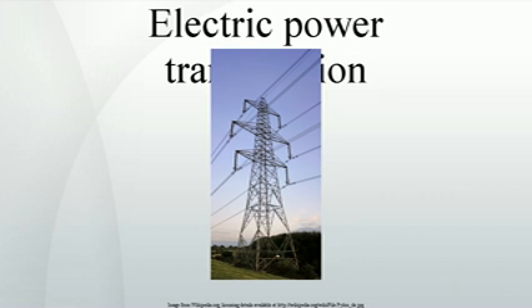Underground cables can be larger diameter because they do not have the constraint of lightweight that overhead cables have, being 100 feet in the air. In general, losses are estimated from the discrepancy between power produced, as reported by power plants, and power sold to end customers. The difference between what is produced and what is consumed constitutes transmission and distribution losses, assuming no theft of utility occurs. As of 1980, the longest cost-effective distance for direct current transmission was determined to be 7,000 kilometers, 4,300 miles.